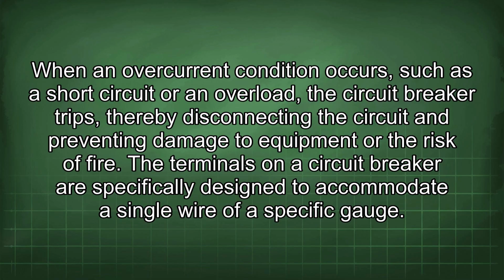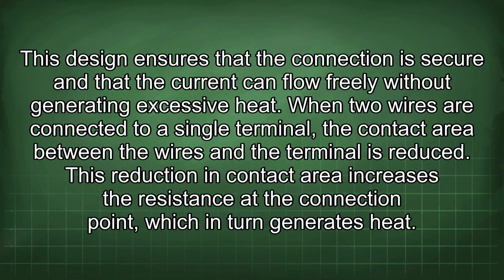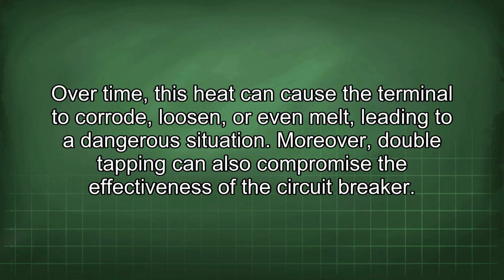The terminals on a circuit breaker are specifically designed to accommodate a single wire of a specific gauge. This design ensures that the connection is secure and that the current can flow freely without generating excessive heat. When two wires are connected to a single terminal, the contact area between the wires and the terminal is reduced. This reduction in contact area increases the resistance at the connection point, which in turn generates heat. Over time, this heat can cause the terminal to corrode, loosen, or even melt, leading to a dangerous situation.